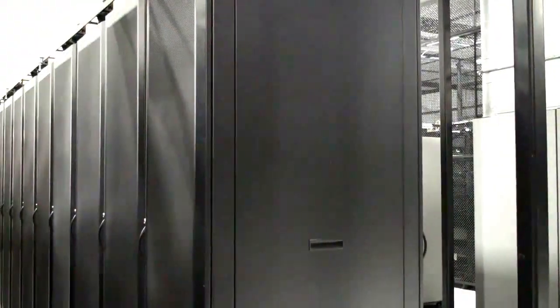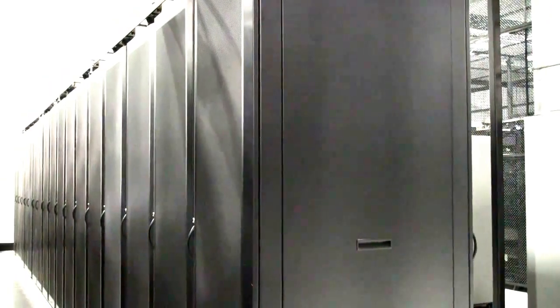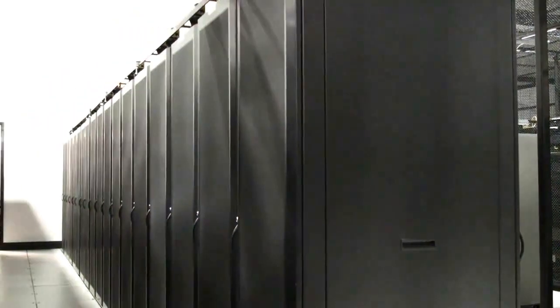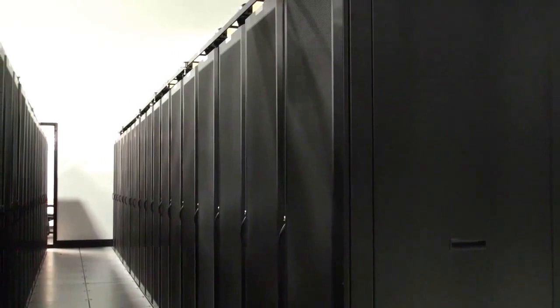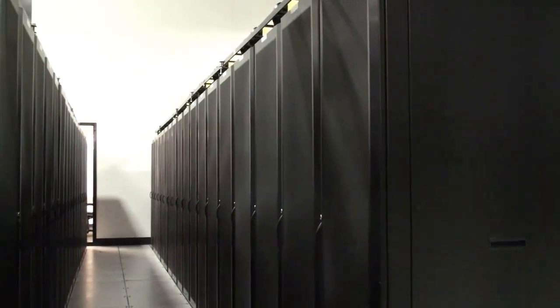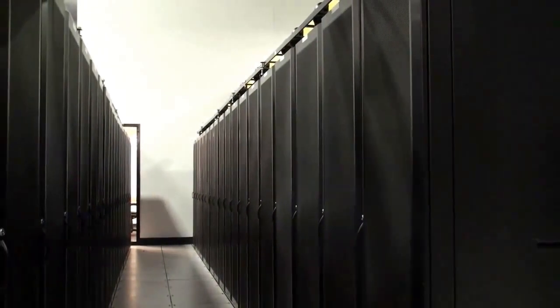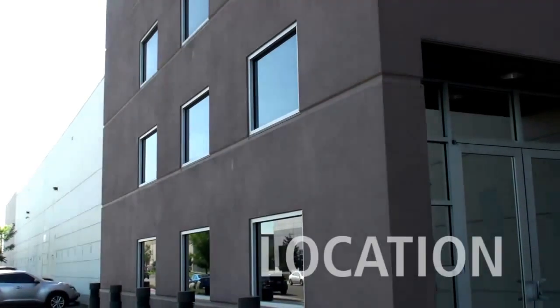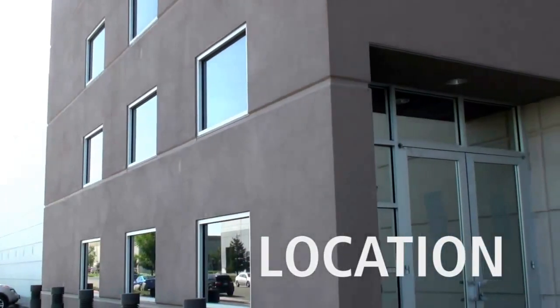power capacity. 1/3 of the raised floor space in Building 2 is currently built out. When fully commissioned, Building 2 will support 96,000 square feet of raised floor space and 24.3 megawatts of critical IT load. Geography was a crucial consideration in locating the data center.